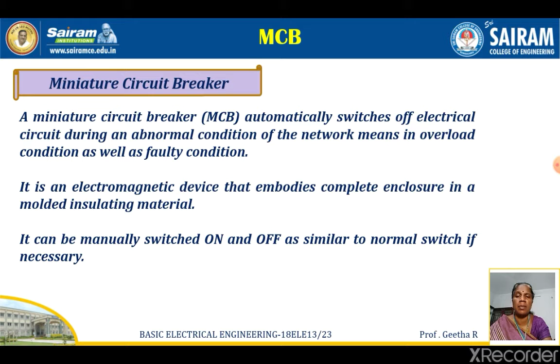In the MCB, there are two arrangements of the operation, that is the magnetic tripping and thermal tripping. The tripping of the circuit is nothing but switching off of the circuit. That is possible by two ways of operation of the MCB, that is magnetic tripping and thermal tripping. Here the diagram shown is for the thermal tripping. Whenever a continuous overcurrent flows through the MCB, the bimetallic strip is heated and deflects by bending.